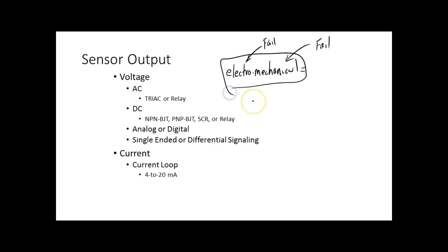Electrically, or it can fail mechanically. Plus, how fast can we switch a relay? Not near as fast as you think. Because once you pick a relay up, let's say it takes 100 volts to pick the relay up. Well, when you drop below 100 volts, that relay is not going to drop out. So relays have what we call a pull-in voltage, and they have what they call a dropout voltage. So it might pull in at 100 volts, but when you pull that thing in, you got to pull that armature up through a gap, right? You understand? And then it comes up and clamps on to the other side of that magnet. Now we're already there. We don't have that space. So it might not drop out.